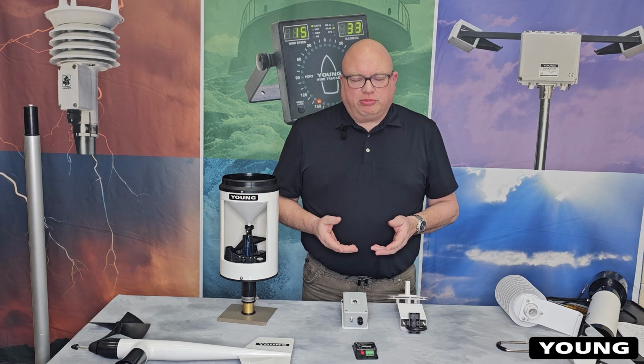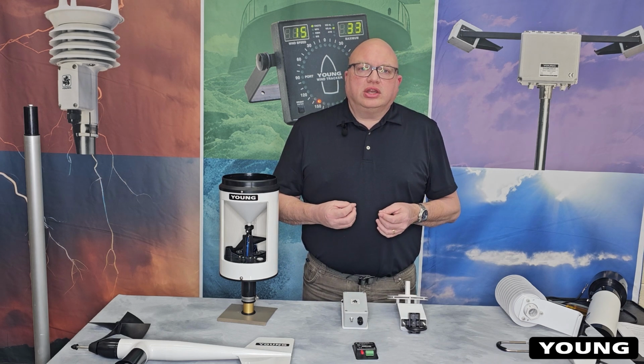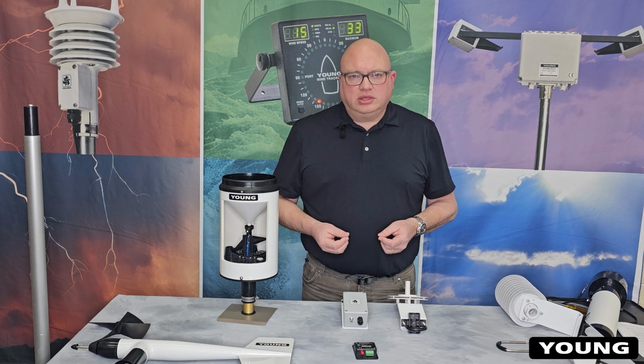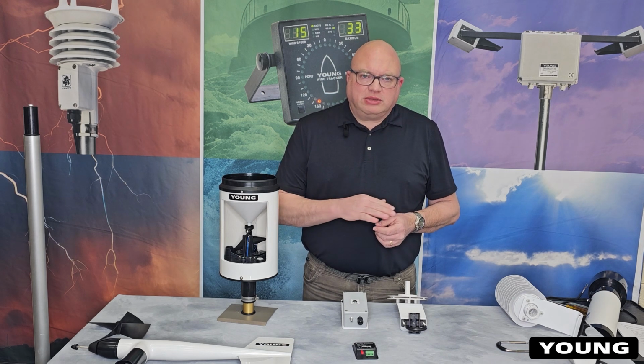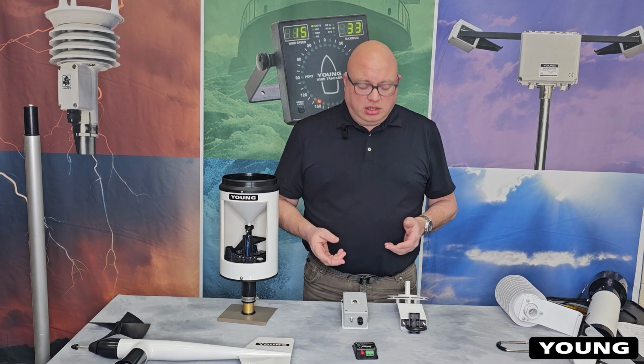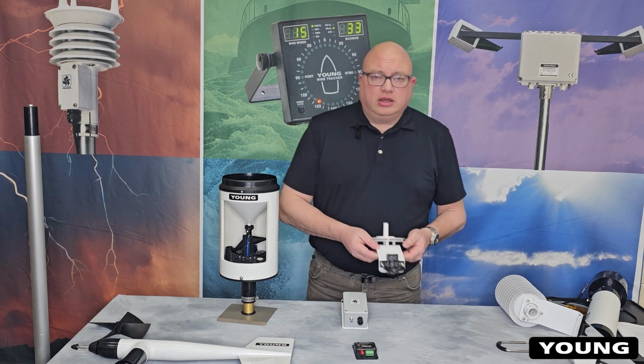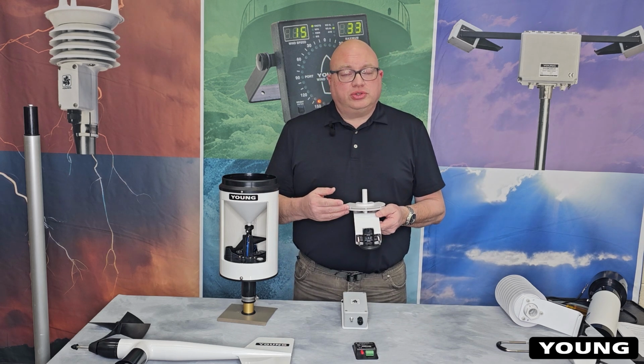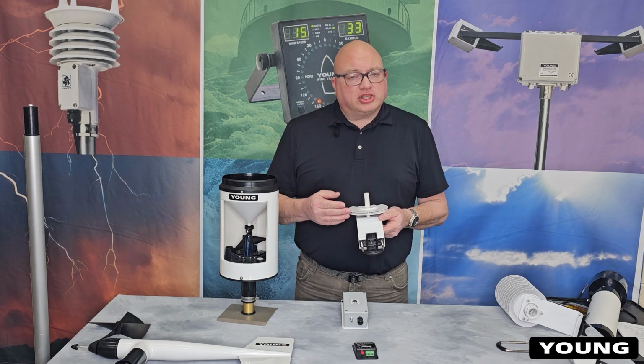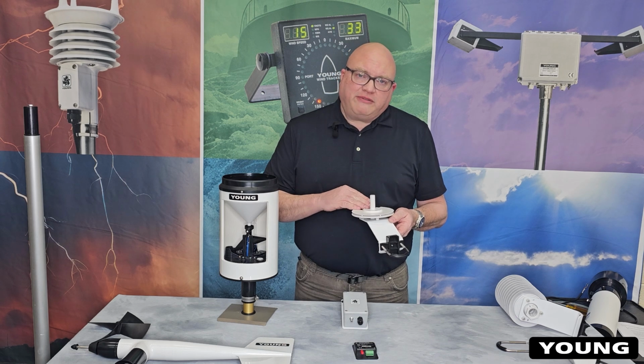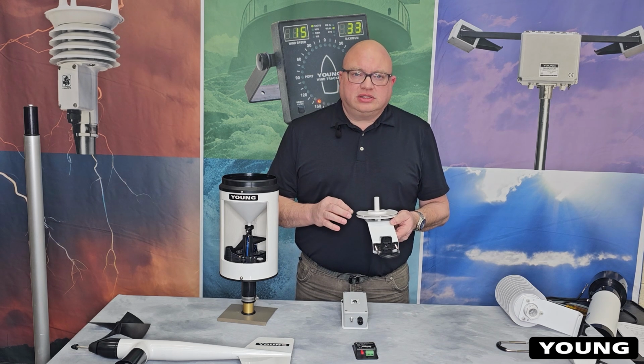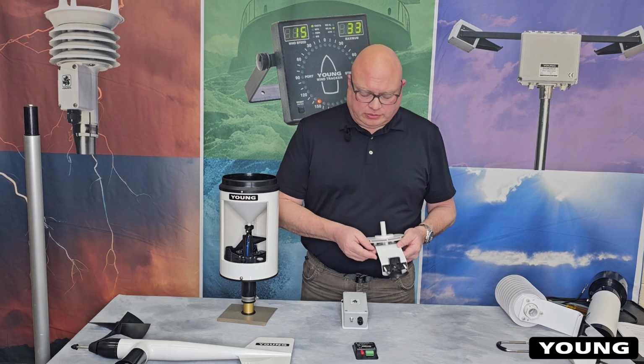When installing a barometric pressure sensor, one thing you need to take into consideration is the effects of wind. As wind blows past the port, it can affect the pressure reading. To prevent that, we have our 61002 pressure port. I'll explain later, but essentially it has baffles inside that mitigate the effects of airflow past the sensor.